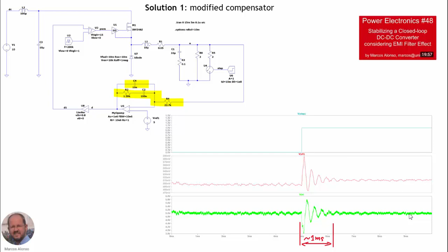So here we have the WinPython script again. In this case, we have the same value for the impedance of the filter, also the same value of the impedance of the DC-DC converter, but changing the expression of the compensator, which is this one now with the values shown here. And then if we do the plotting, we obtain this Bode diagram, in which if we look at the value at minus 180 degrees of the magnitude of the function f, we can see that it is lower than 0 dBs. So we have a stable system.